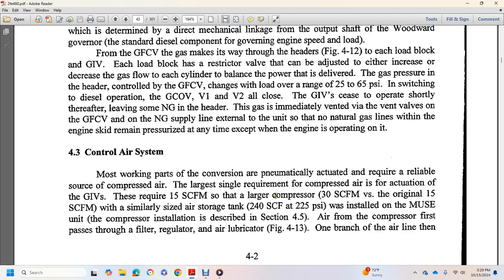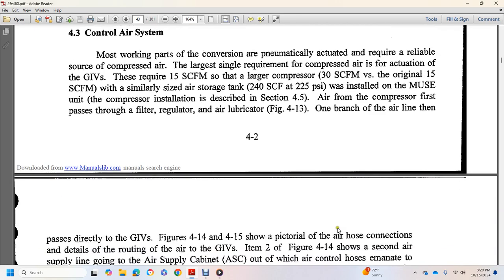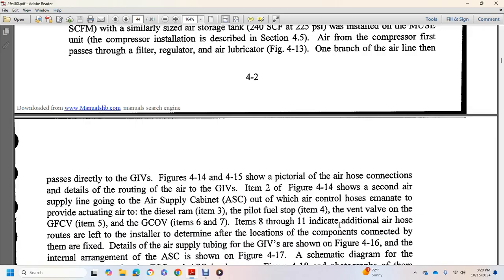A similarly sized air storage tank of 240 SCF at 225 psi is installed with the unit, with the compressor installation described in section 4.5. Air from the compressor must pass through the filter, regulator, and air lubricator, figure 4.13. One branch of the airline then passes directly to the gas inlet valves, figures 4.14 and 4.15, with a pictorial of the air hose connections showing the detailed routing of the air to the gas inlet valves.